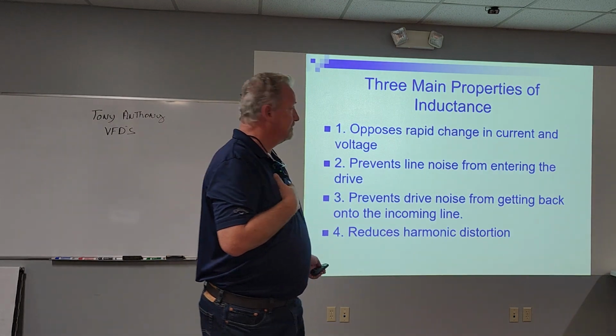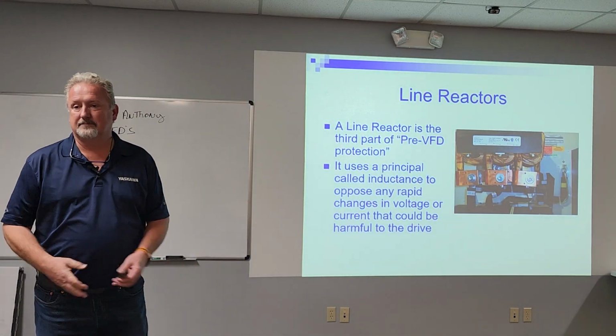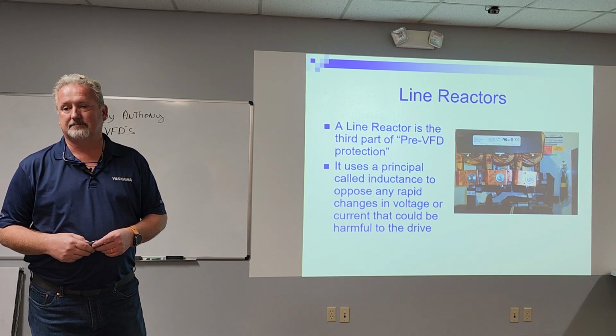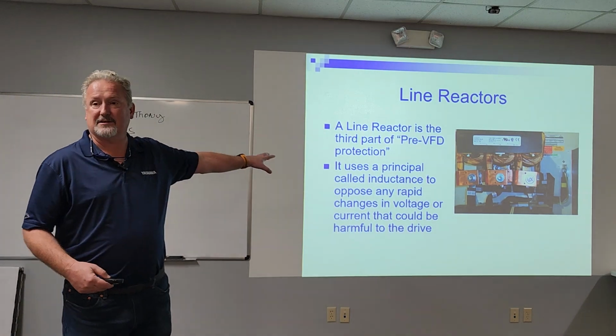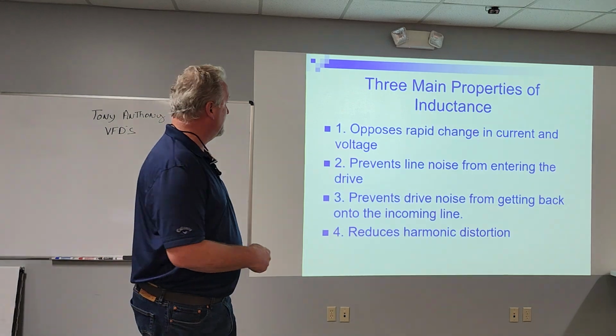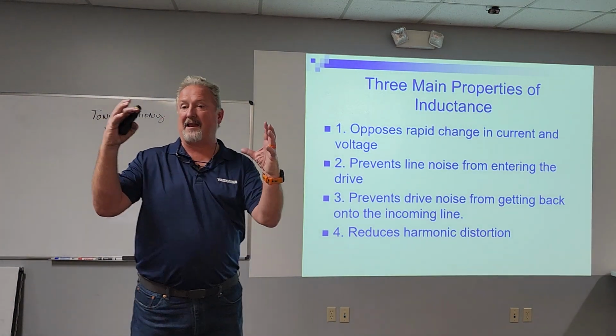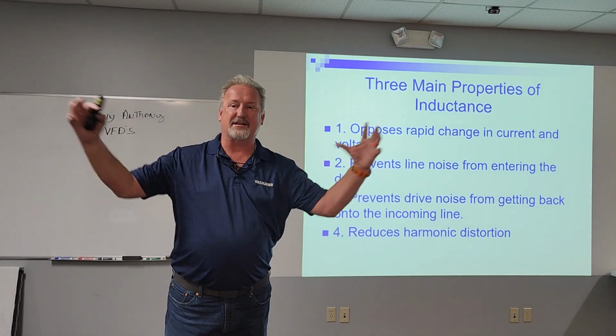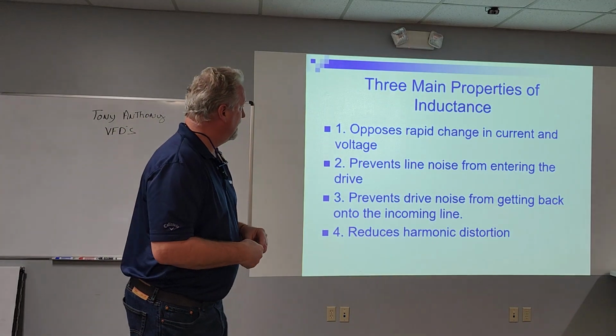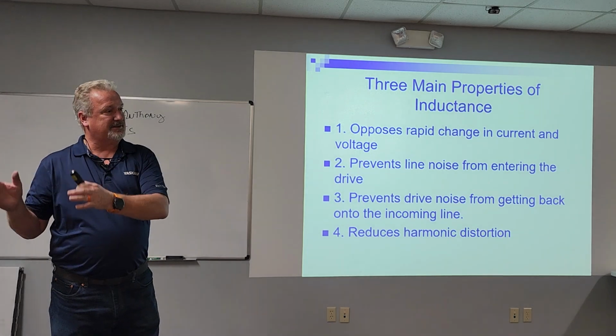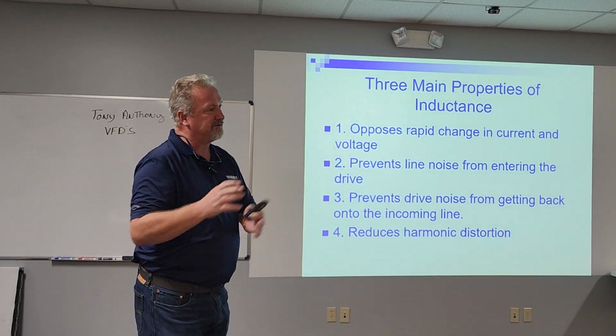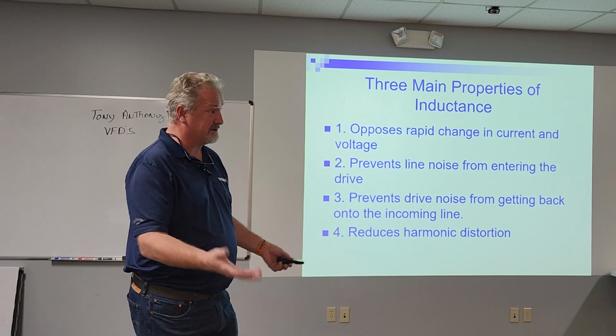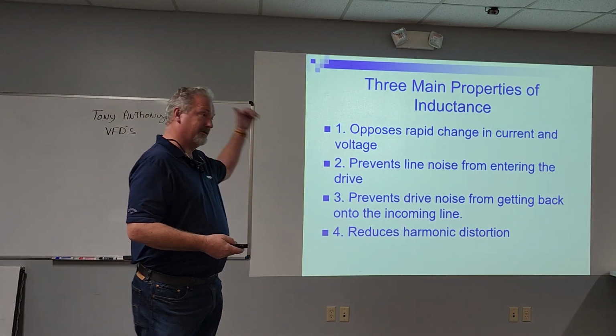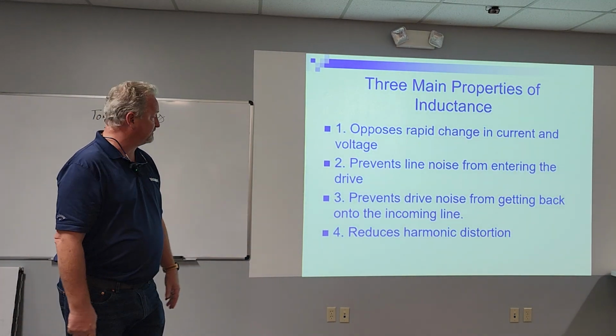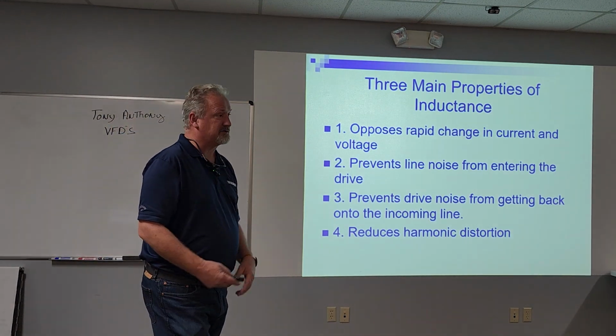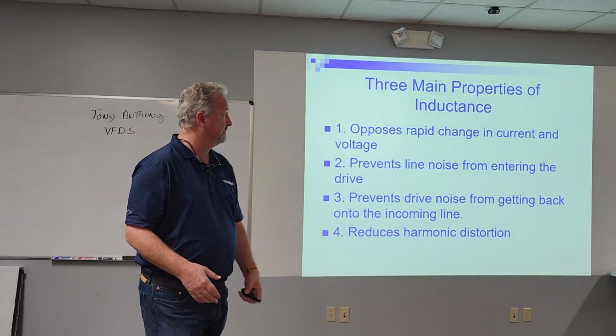On that reactor, is it protected in any way to clamp that voltage? Well, that's what the inductance does. It will clamp that voltage. It naturally opposes rapid changes because it creates a big magnetic field. With any quick change, it's going to have a tendency to suppress it. It also prevents noise coming from other equipment from getting into the drive. That's usually not a problem we worry about too much, but it does do that. It prevents drive noise from getting back on the incoming line. That's what we've been sitting here talking about for the last 10 minutes. And it reduces the harmonic distortion that we talked about. It actually cuts it in about half.